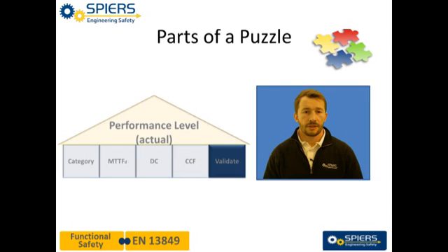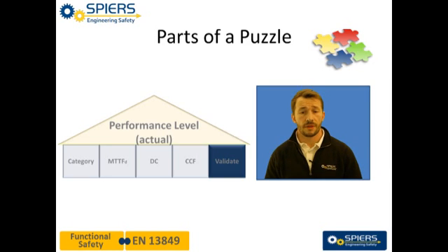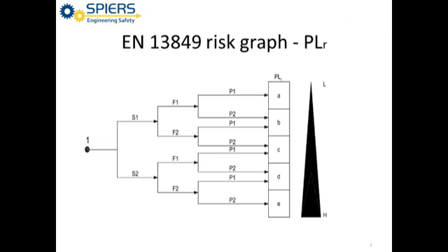During the validation and verification, you will demonstrate that the combination of the safety-related parts and control system for each safety function meets all relevant requirements and risk reductions identified. The risk reduction required can be identified using the risk graph from Annex A.